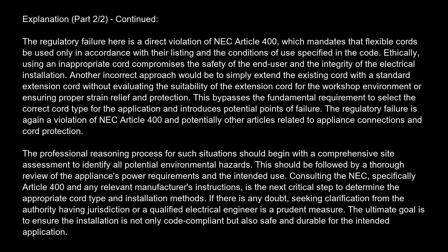The professional reasoning process for such situations should begin with a comprehensive site assessment to identify all potential environmental hazards. This should be followed by a thorough review of the appliance's power requirements and the intended use. Consulting the NEC, specifically Article 400, and any relevant manufacturer's instructions, is the next critical step to determine the appropriate cord type and installation methods. If there is any doubt, seeking clarification from the authority having jurisdiction or a qualified electrical engineer is a prudent measure. The ultimate goal is to ensure the installation is not only code compliant, but also safe and durable for the intended application.